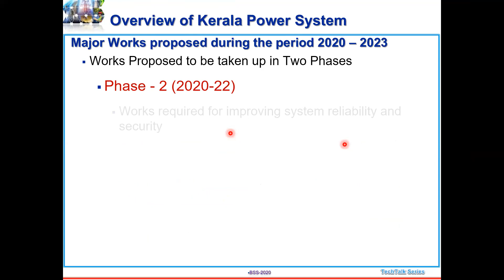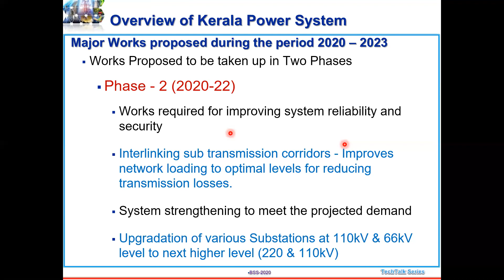The phase 2 works are basically meant for improving system reliability and security. For all 33 kV lines we are planning a ring system, and for upgrading the existing 66 kV to 110 kV and 220 kV. So it's basically for strengthening the existing network. After meeting the security criteria, we'll go in for improving the existing network so that we will have 24/7 supply without any interruption. Even in the outage of one of the feeders or transformers, we will not face any system constraints.